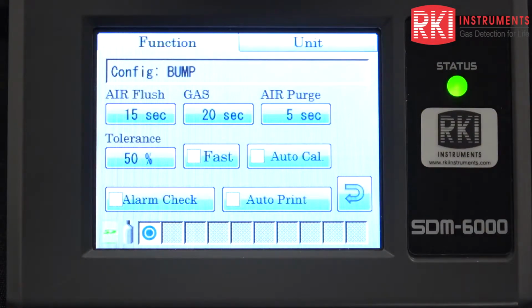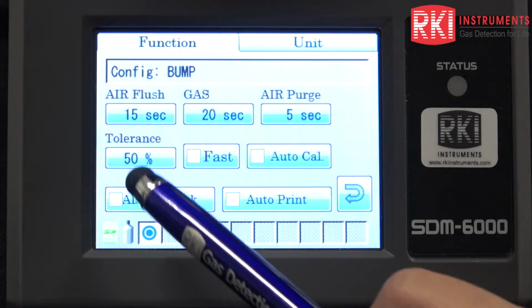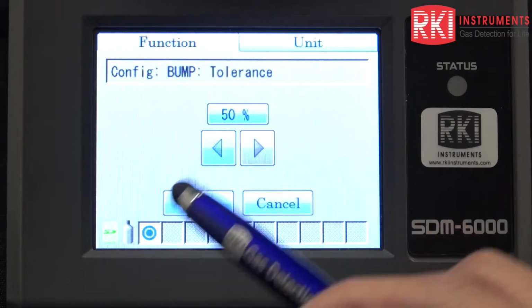Let's go over bump first. So it will show air flush, gas, and air purge. Air flush is in the beginning doing the air cal and zeroing everything out. The gas is the 20 seconds it's going to run your gas through, and air purge is going to be the amount of time that it's going to purge out the instrument and clear out the toxic gases that are running through it. There's also a tolerance, which you can change.